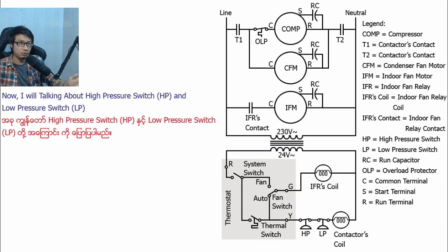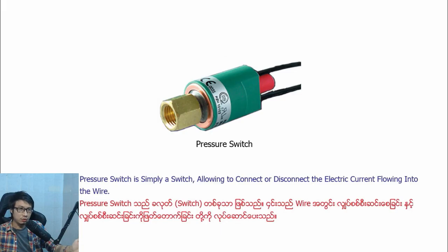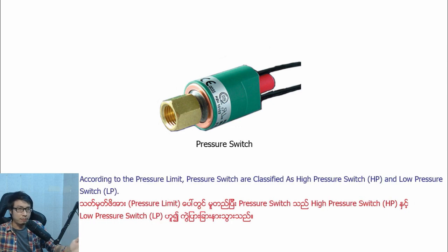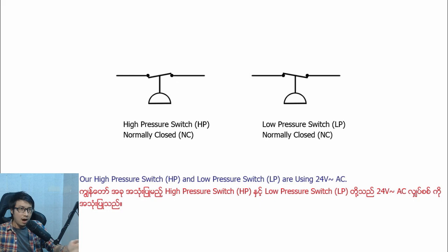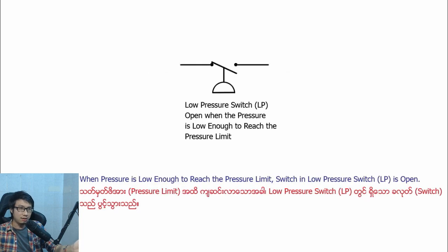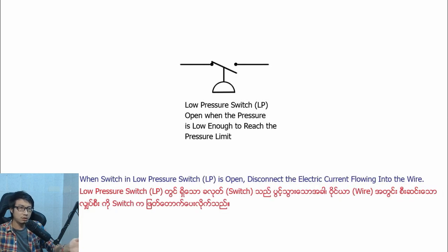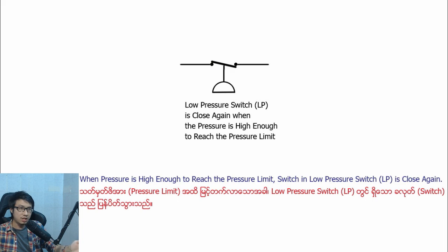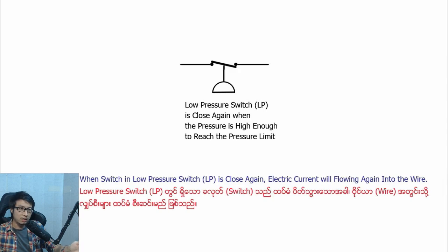Now I will talk about the high-pressure switch and low-pressure switch. A pressure switch is simply a switch that allows connecting or disconnecting the electric current flowing into the wire according to the pressure limit. Pressure switches are classified as high-pressure switch and low-pressure switch. Our high-pressure switch and low-pressure switch are using 24V AC. When pressure is low enough to reach the pressure limit, the low-pressure switch opens and disconnects the electric current. When pressure rises high enough, the low-pressure switch closes again and electric current flows again.